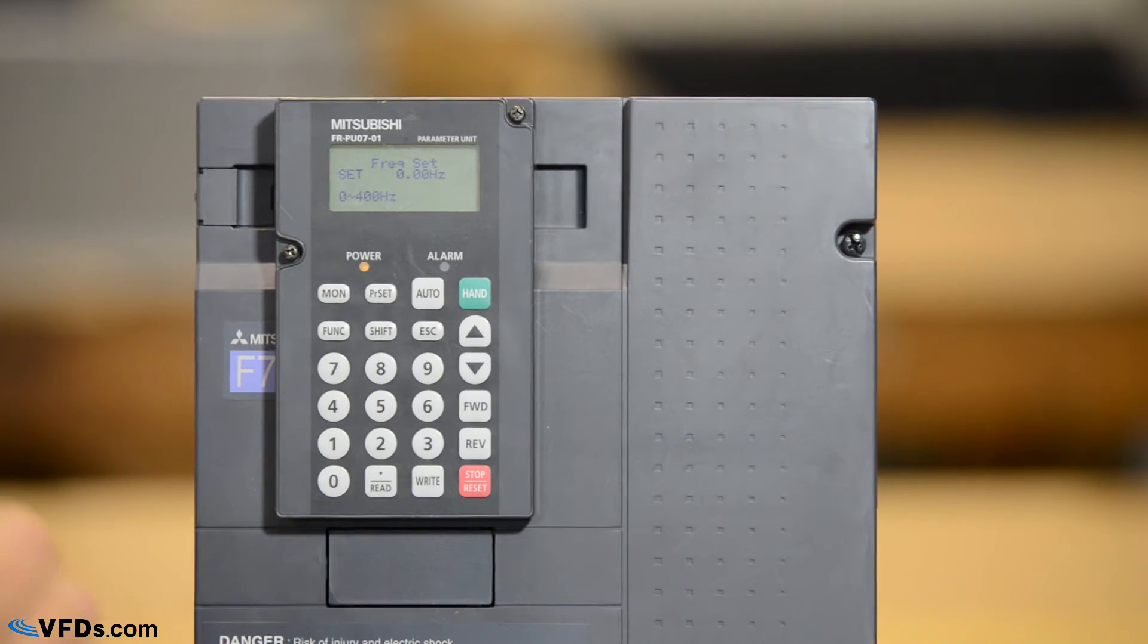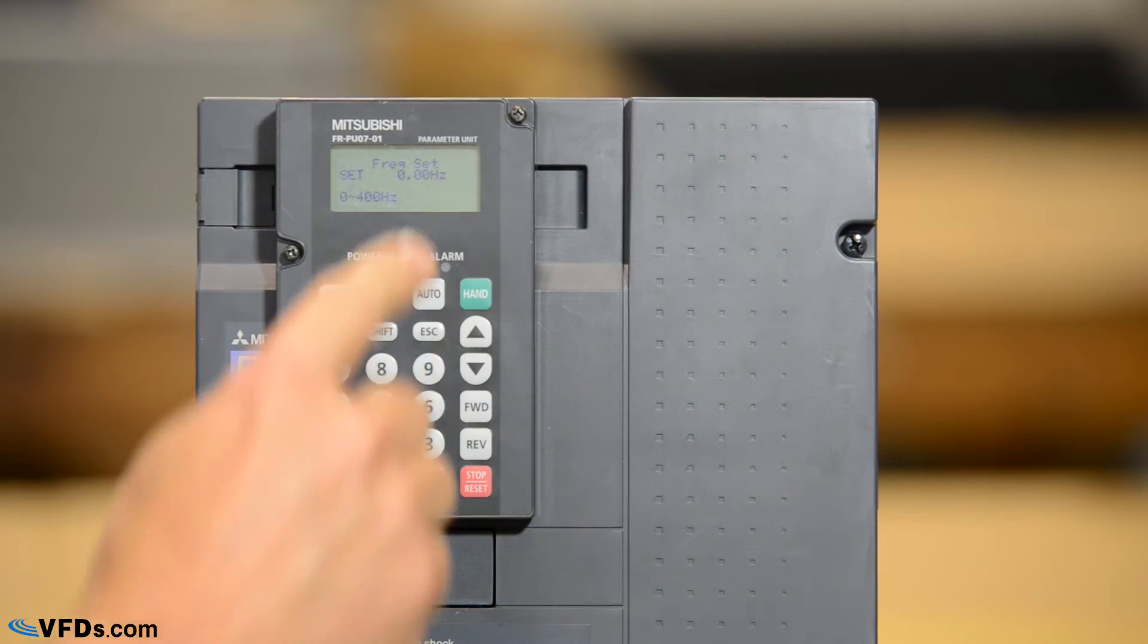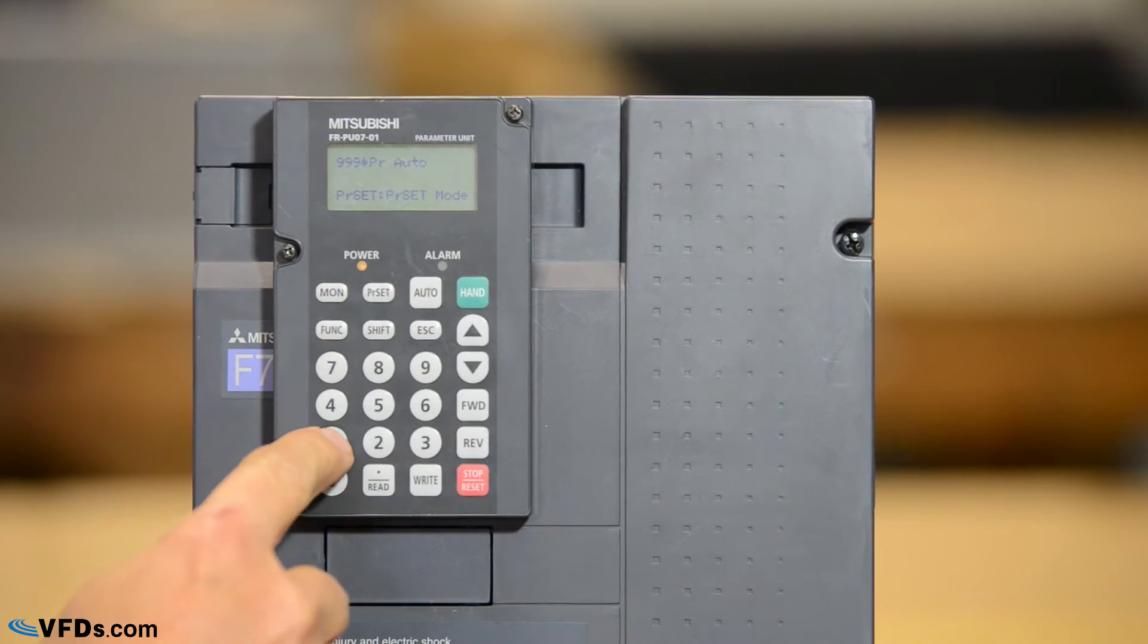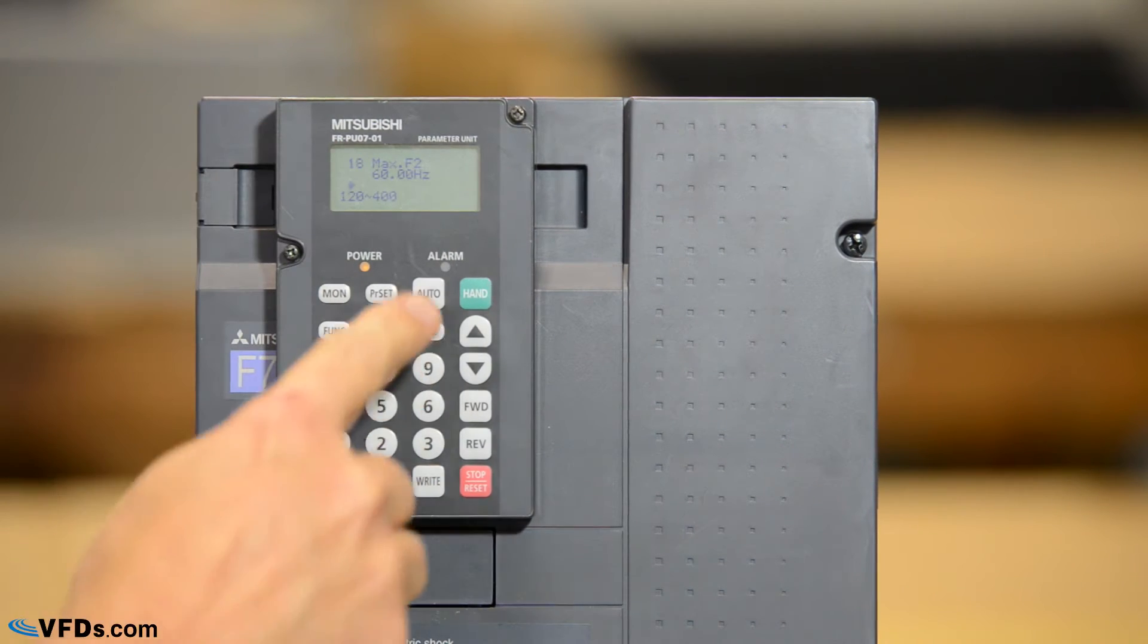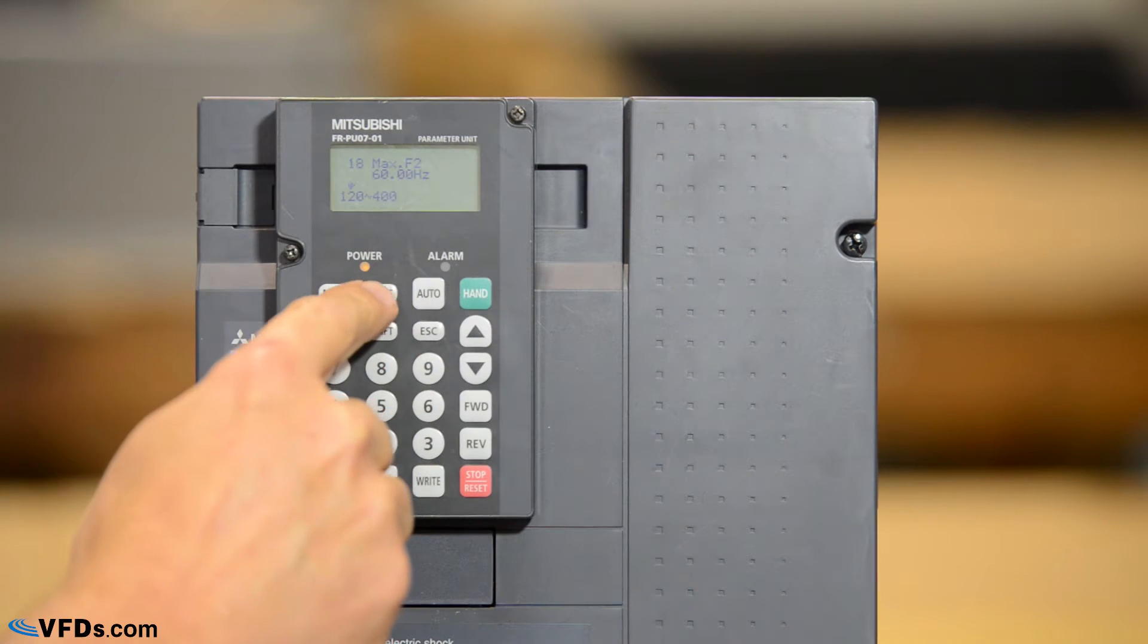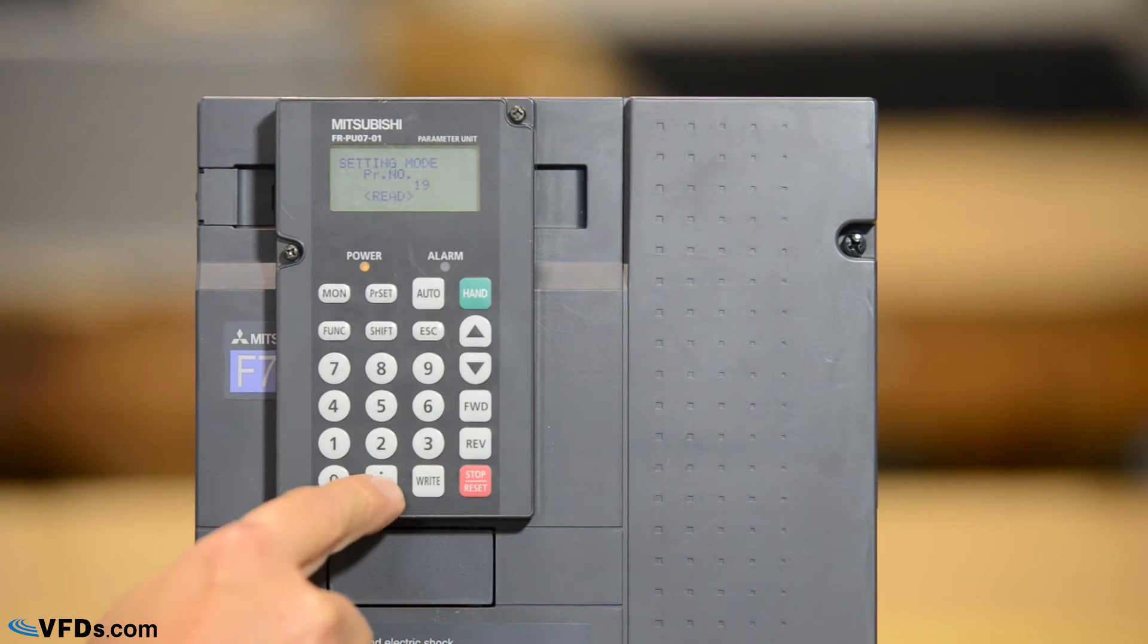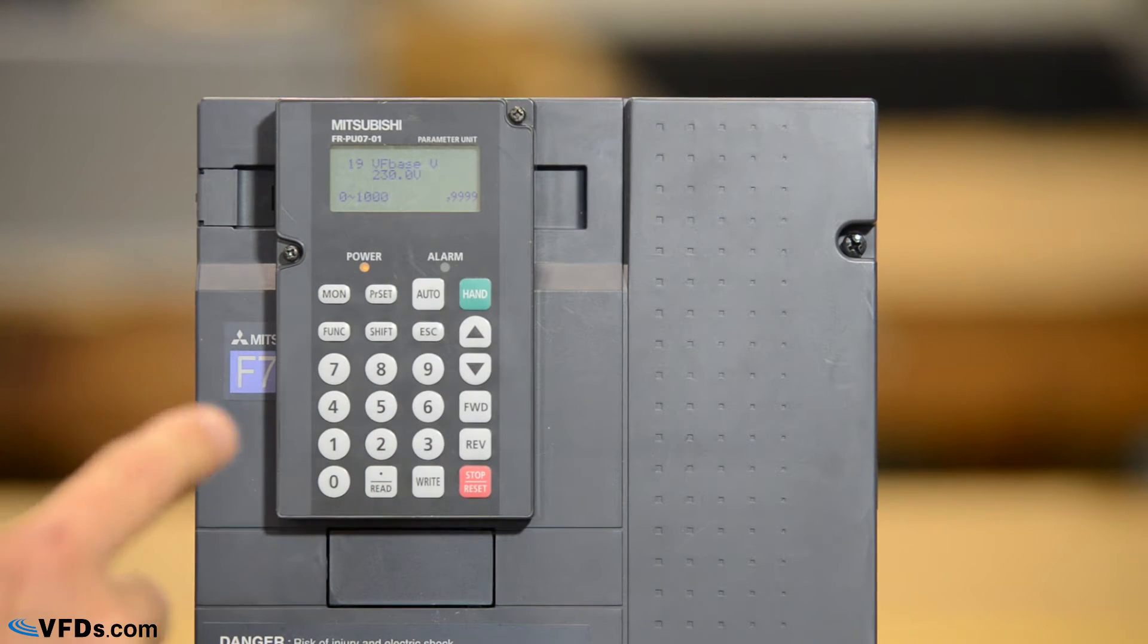Now the first thing you should program under drive is the volts per hertz so let's do that. The voltage is parameter 19 so I simply push parameter set 19 read and it's set for 60. I made a little mistake there. That's parameter 18. Let's go to parameter set 19 and read and there it is. It's set for 230 volts.